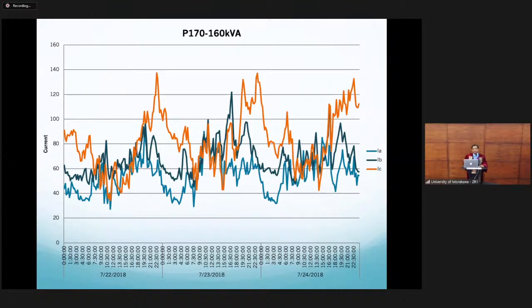What CEB and LECO do is, periodically, every six months or yearly, try to shift loads, the houses, from the highly loaded phase to a lower loaded phase. But this is never a 100% successful task. One issue is that customer loads vary, and it's now more aggravated by the presence of solar photovoltaic generation on rooftops. So it is not possible to do this manually in a perfect way.